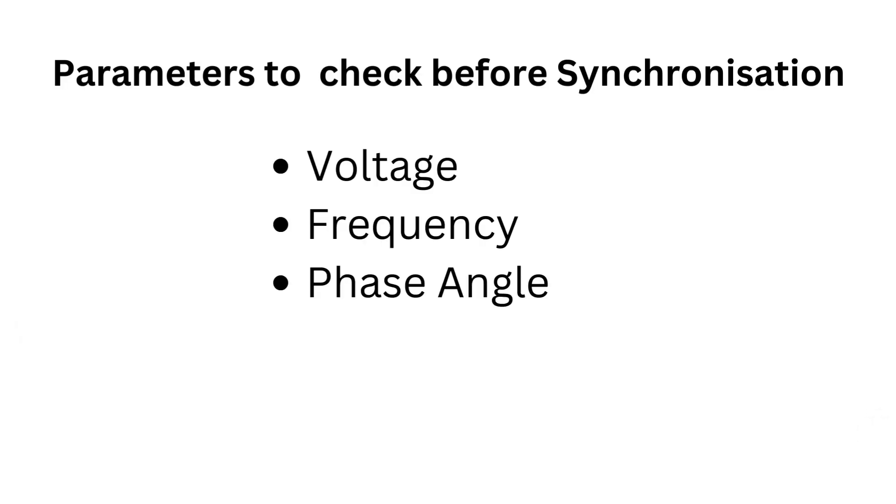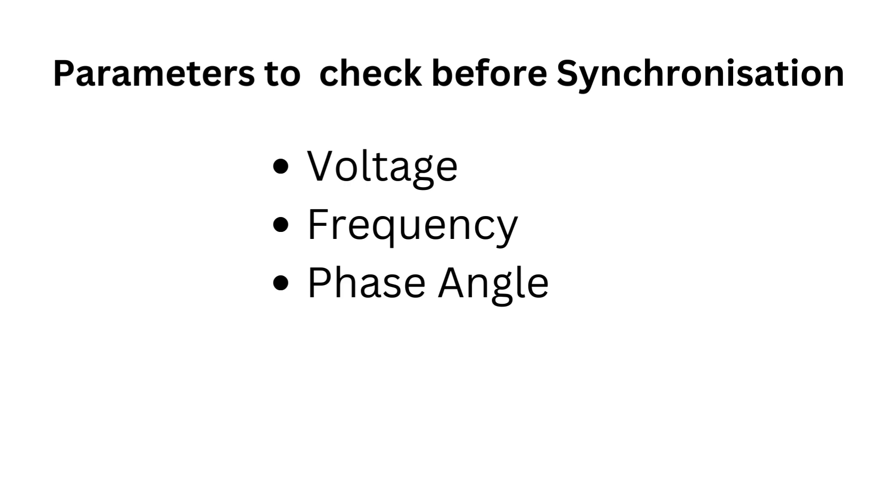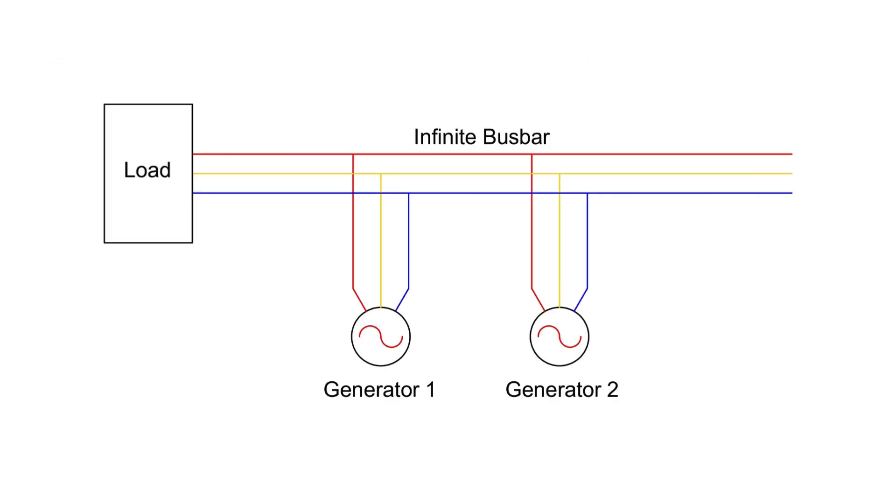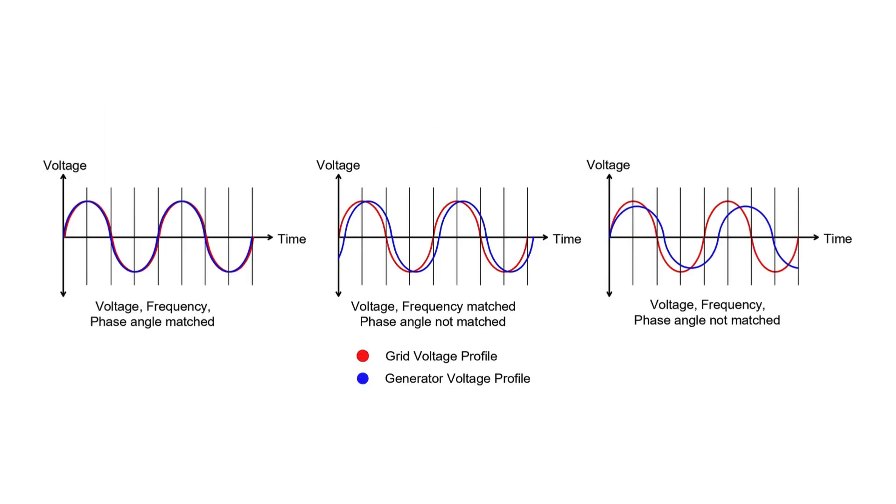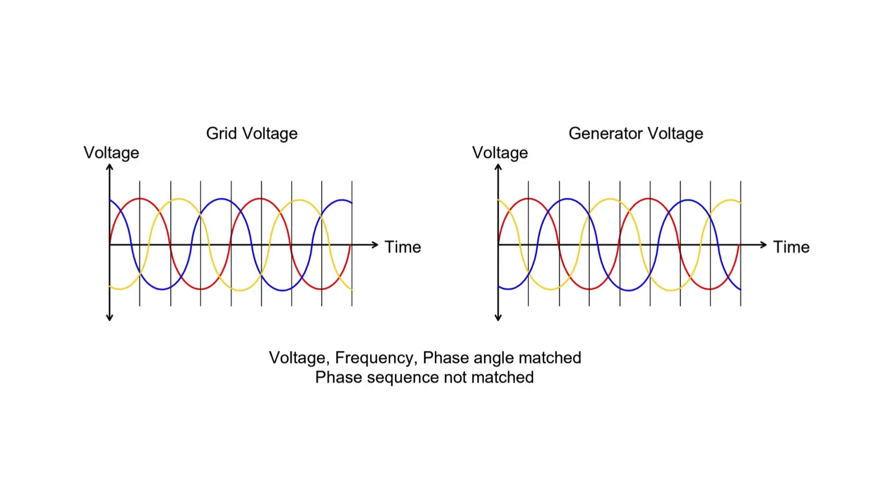Now, why do we consider these parameters like voltage, frequency and phase angle when connecting a generator to the grid? Imagine two generators are operating in parallel with a load connected to their terminals and you need to connect a third generator in parallel. The first two are running generators and the one you're connecting is the incoming generator. The voltage profile of the incoming generator should match the running generators.